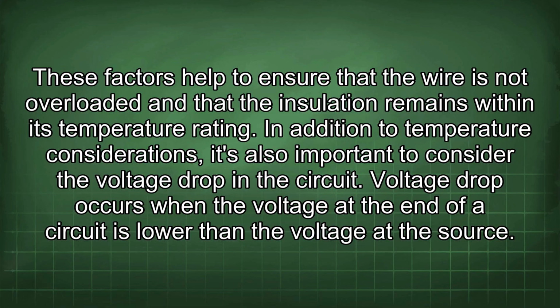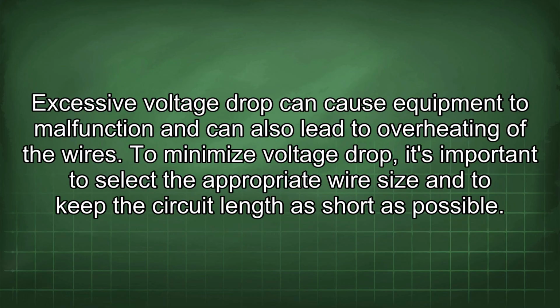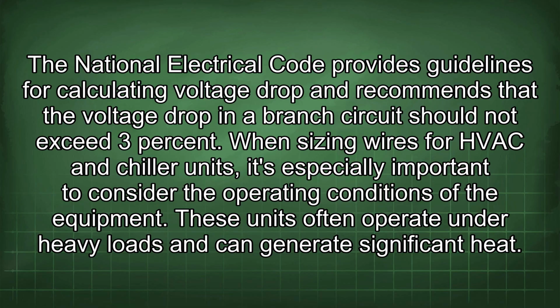In addition to temperature considerations, it's also important to consider the voltage drop in the circuit. Voltage drop occurs when the voltage at the end of a circuit is lower than the voltage at the source. Excessive voltage drop can cause equipment to malfunction and can also lead to overheating of the wires. To minimize voltage drop, it's important to select the appropriate wire size and to keep the circuit length as short as possible. The National Electrical Code provides guidelines for calculating voltage drop and recommends that the voltage drop in a branch circuit should not exceed 3%.